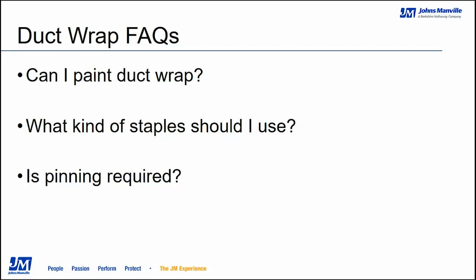The next question that we get is, what kind of staple should I use? And you should use an outward clenching staple every 6 inches on center for putting together duct wrap. You want to make sure that they go out, and when you put an outward clenching staple in, it'll go into the FSK facing and it'll turn itself outward actually and grab on and hold to those 2 layers of foil that you're stapling together.